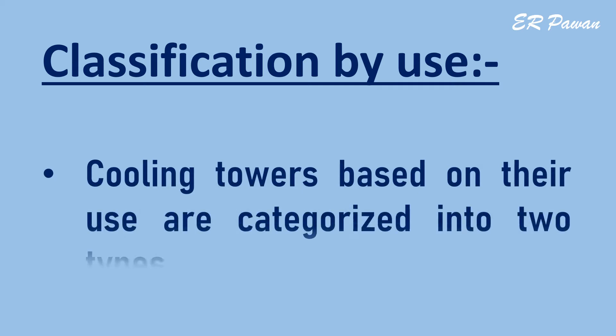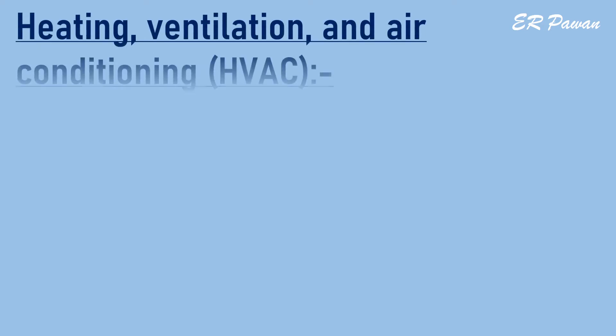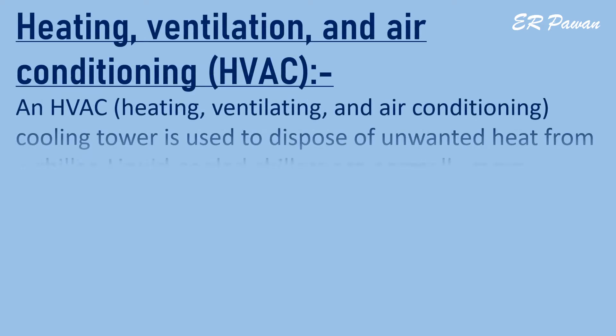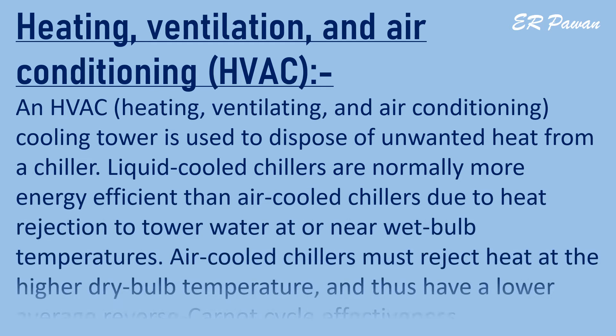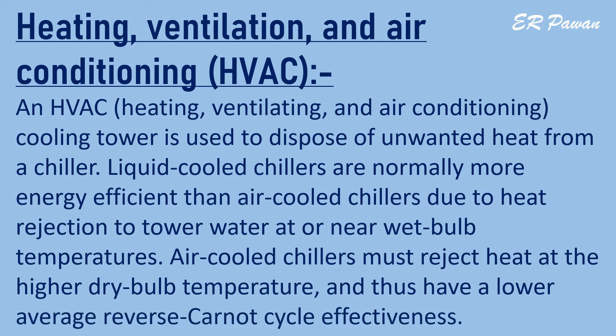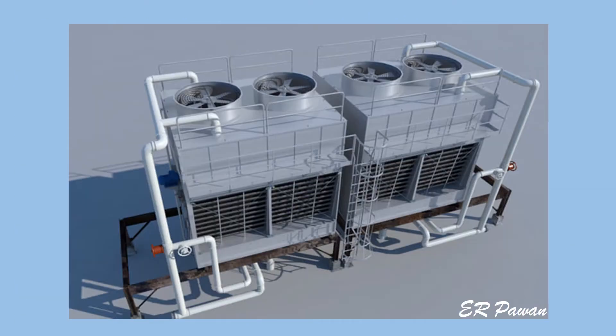Cooling towers based on their use are categorized into two types. HVAC — heating, ventilating, and air conditioning — cooling towers are used to dispose of unwanted heat from a chiller. Liquid-cooled chillers are normally more energy efficient than air-cooled chillers due to heat rejection to tower water at or near wet bulb temperatures. Air-cooled chillers must reject heat at the higher dry bulb temperature and thus have a lower average reverse Carnot cycle effectiveness.